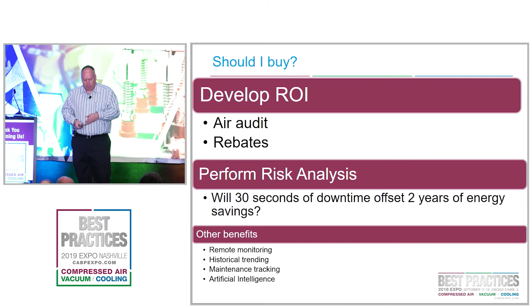For instance, if you have centrifugal compressors and you're in a blow-off state, what if you slow down the water flow to the compressor, where you're not making as much air, and you take some load off of your cooling tower or chiller? You're making less air, and all these things work together. So it's very predictive and very intuitive, but I think that's the next step we're going to see: the same type of multiple algorithms and considerations looking at a complete compressor room to make smart decisions to optimize compressed air production.